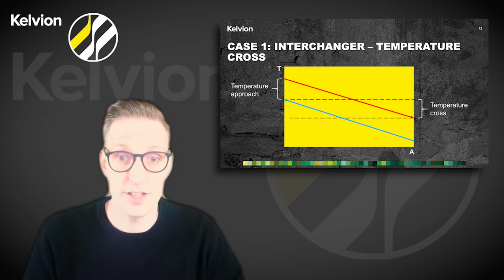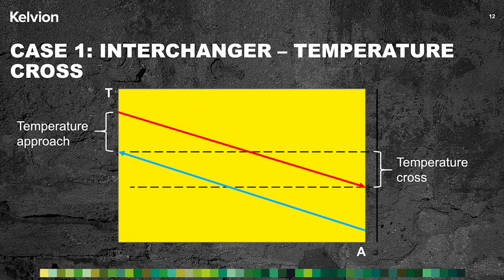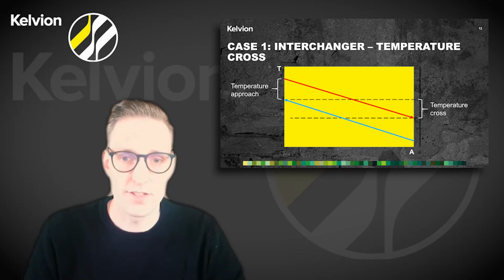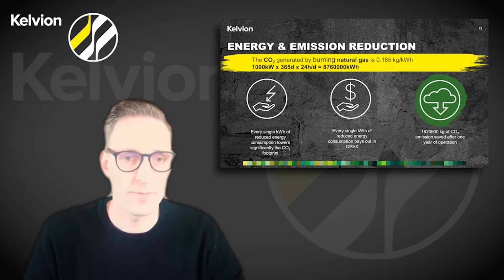K-block heat exchangers are using the cross-counterflow principle. This is extremely beneficial for interchangers in heat recovery applications. This and the turbulent flow enables the K-block to achieve temperature crosses within 1 unit. A closest possible temperature approach between 5 to 10 degrees is possible in process applications, but it varies of course depending on the specific application. All this leads to the conclusion that the K-block is a very powerful interchanger.